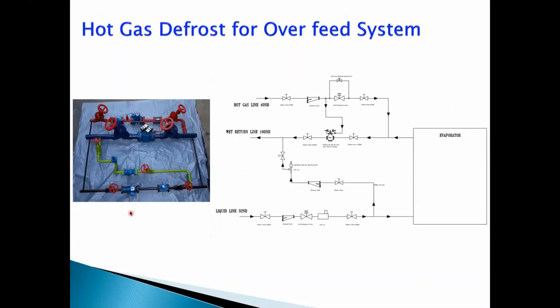As I was talking about hot gas defrosting, you can make a hot gas defrosting circuit. I just explained how it works, so I'll not go into more detail. Here, this very important part which I'll talk about is the valve in the wet return line. The valve in the wet return line is on the low pressure side, so it has to have a very, very low or minimum pressure drop. So most of the time it is a gas powered valve.